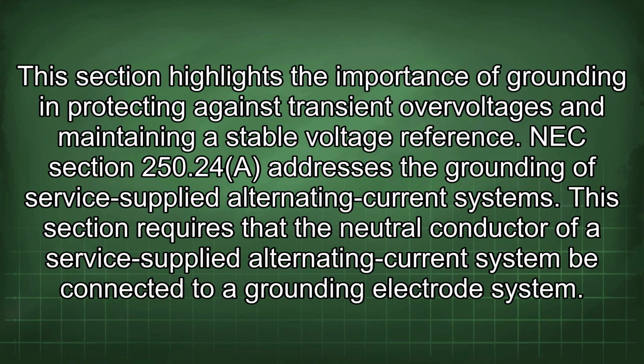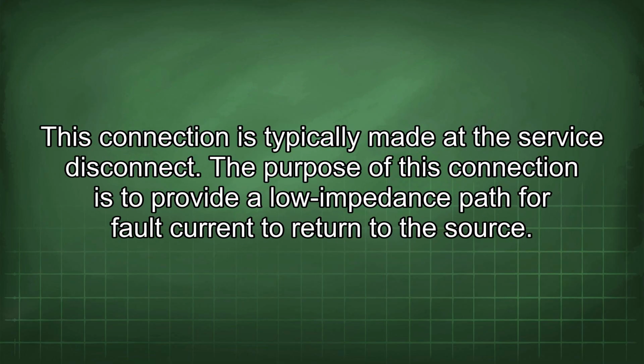This section highlights the importance of grounding in protecting against transient overvoltages and maintaining a stable voltage reference. NEC section 250.24 addresses the grounding of service-supplied alternating current systems. This section requires that the neutral conductor of a service-supplied alternating current system be connected to a grounding electrode system. This connection is typically made at the service disconnect. The purpose of this connection is to provide a low impedance path for fault current to return to the source.